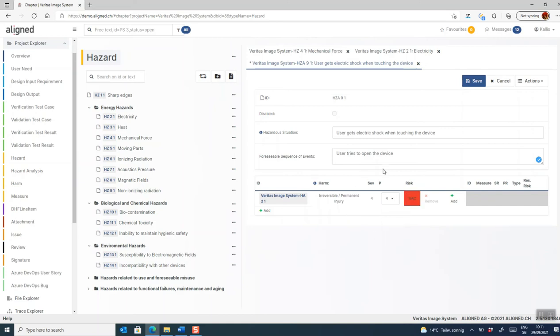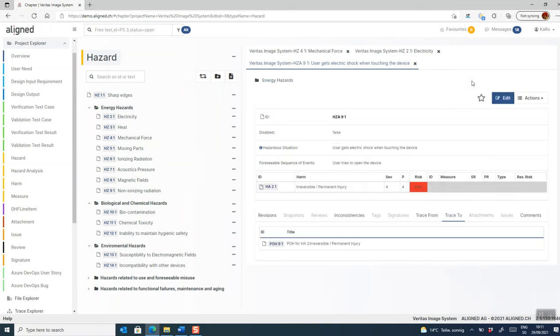And we can see that the software, using a risk calculation that is, of course, individual to each medical device, deems that the combination of severity and probability for this device leads to a non-acceptable risk. So that is how you can identify and create and evaluate risks.